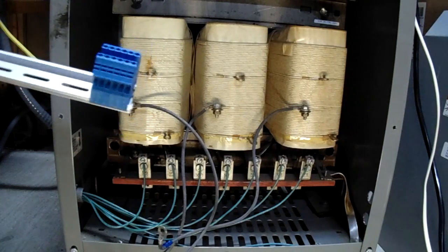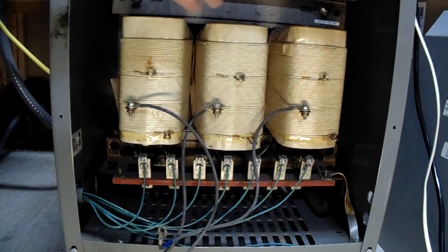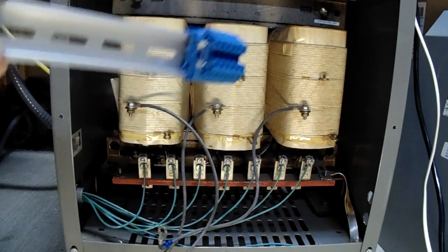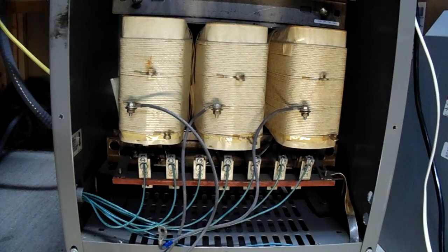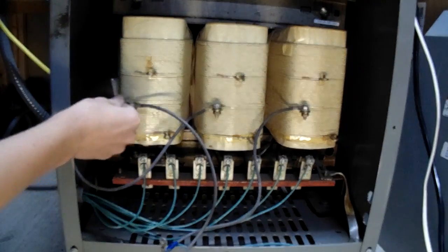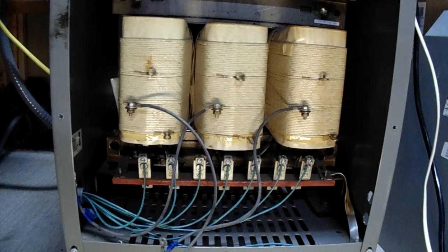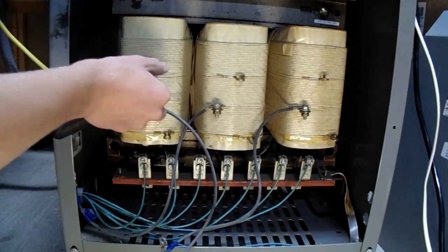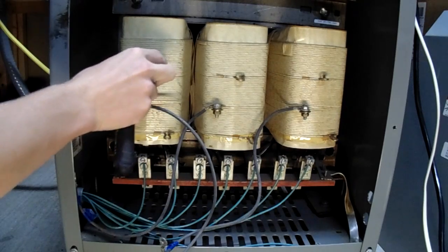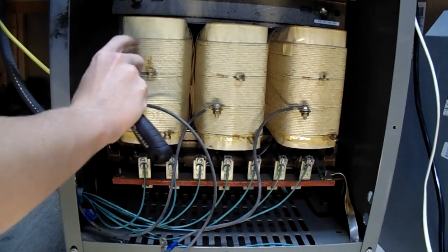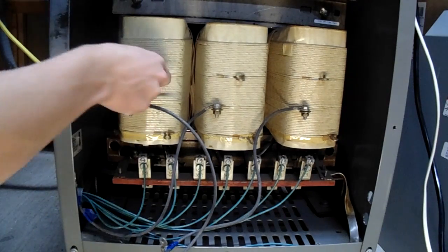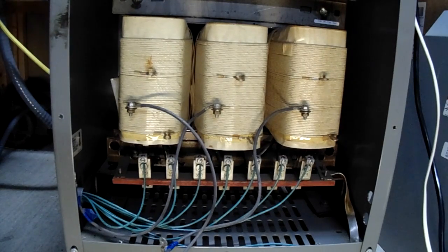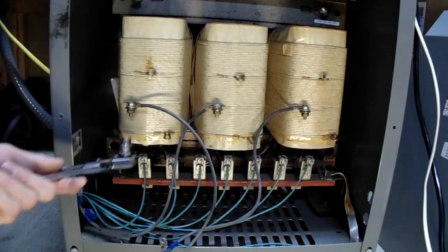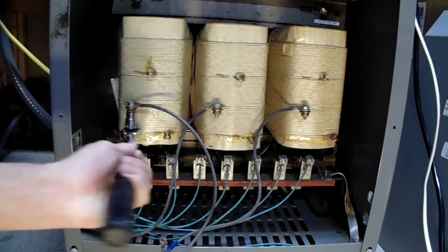So anyways, a couple other things you could do. You could mount one of these in your enclosure across the top, obviously not on the core. You could mount one of these DIN rails with a couple connectors in your housing to connect these two, or you can just do what I'm doing, which is just going to connect them from lug to lug. And something you want to be careful with on these style of taps is these are actually parts of the winding. So if you break one of these off, well, you'll lose that winding, and you'll have to get it rewound, or you can just kiss your transformer goodbye. So in this case, I'm going to be very careful not to break that off.